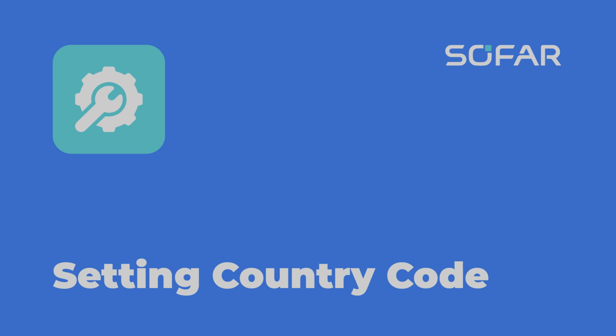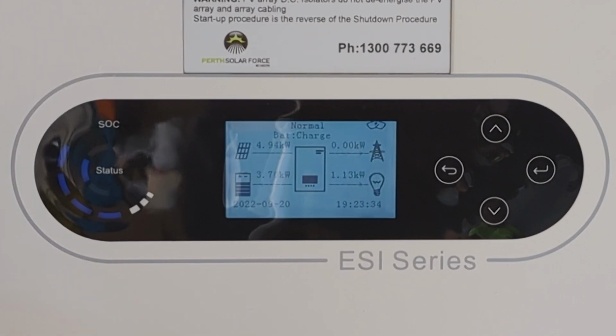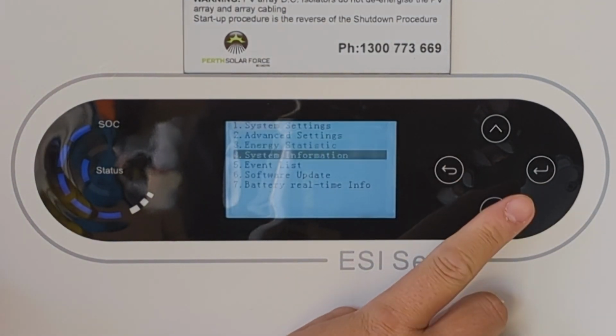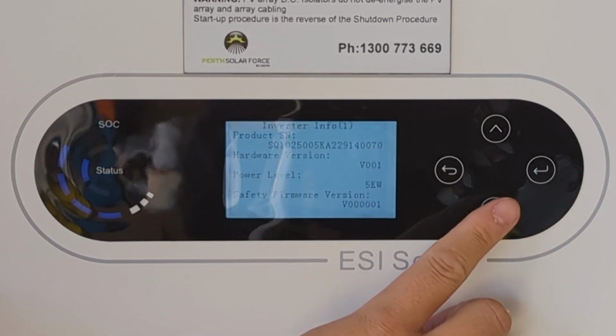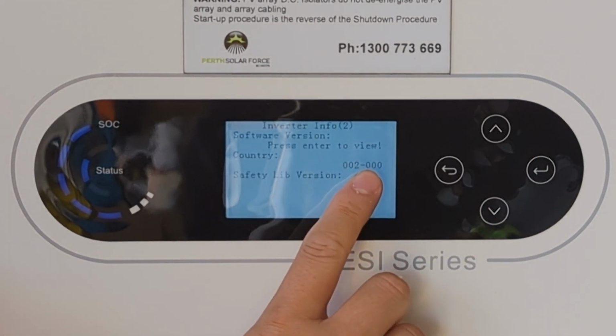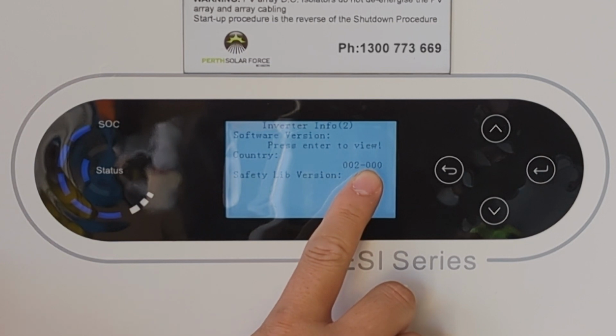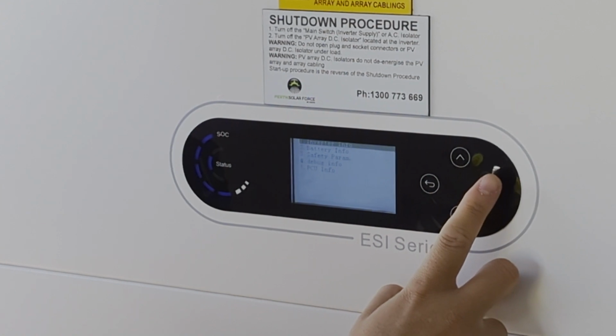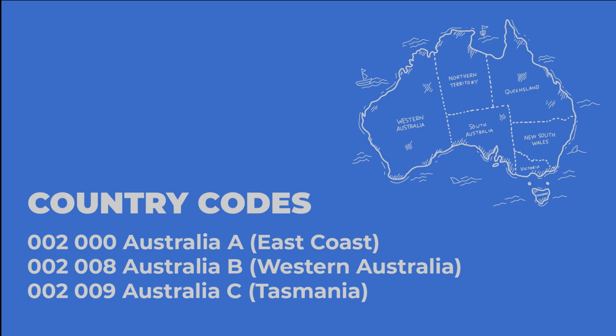When the inverter is running, set the following parameters. First, we set the country code. Select the option System Settings, then System Information, then Inverter Info. Scroll down until you see the country code and check if it is currently set to the correct code for your area. If not, simply correct the code and confirm. The country codes are 002 000 for the eastern states, 002 008 for Western Australia, and 002 009 for Tasmania.